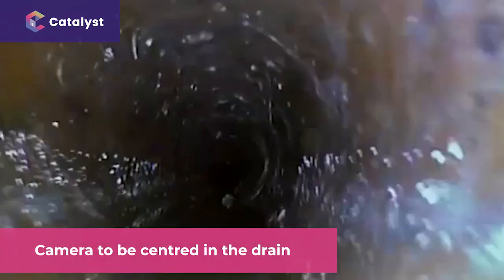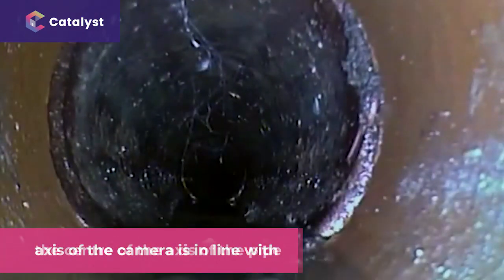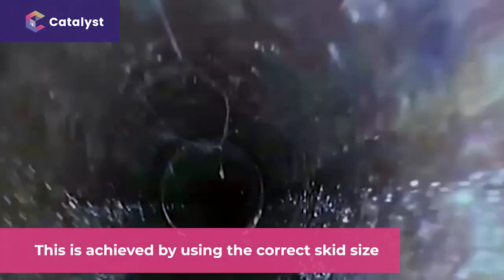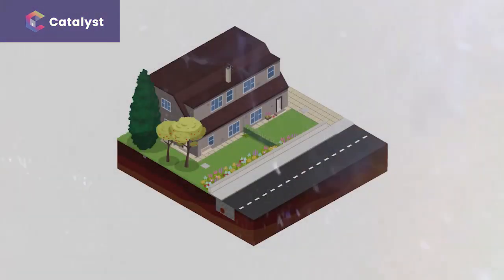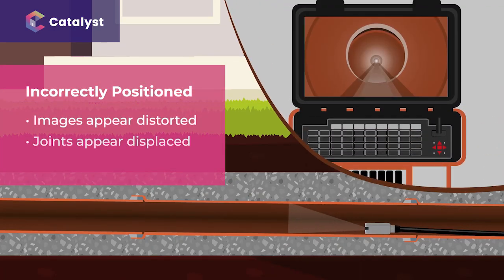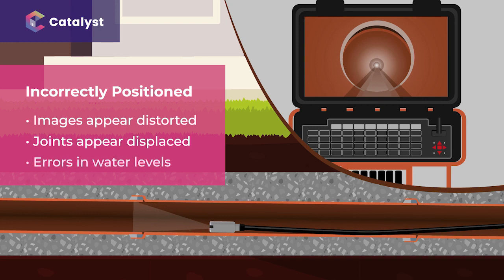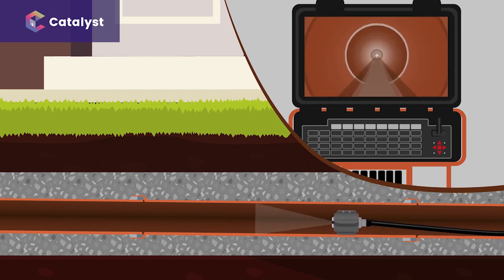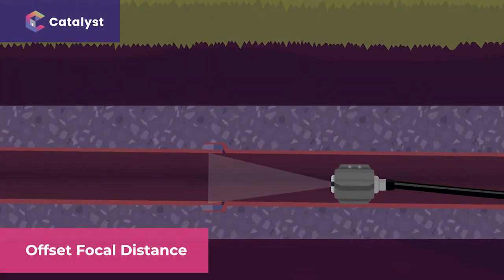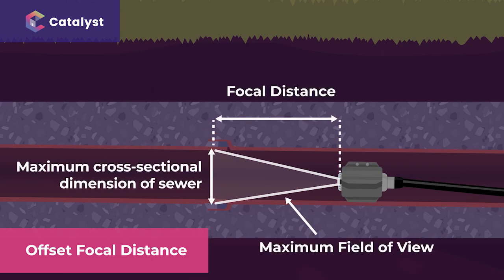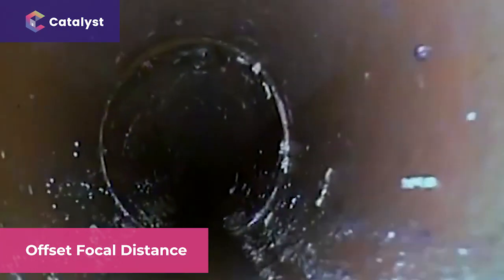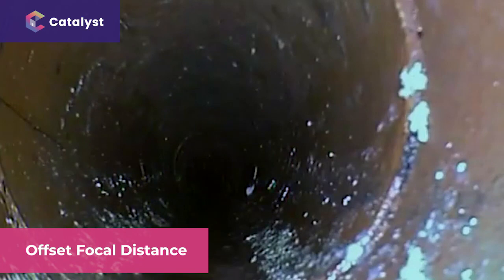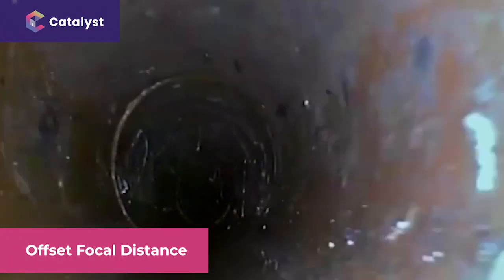It's very important for cameras to be centred in the drain. It means the axis of the camera is in line with the centre of the axis of the pipe. This is achieved by using the correct skid size for the pipe. If the camera is too high or too low, the images recorded can be distorted, making joints appear displaced when they're not, and resulting in errors in the estimation of water levels. This can happen, for instance, if a 100 millimetre skid is being used in a 150 millimetre drain. The offset focal distance also needs to be considered — in basic terms, the location you're seeing on the monitor screen is not the actual location of the camera. This matters when marking up for a liner or a patch repair that needs to cover a fault at a precise point such as a junction, rest bend, or patch liner repair.